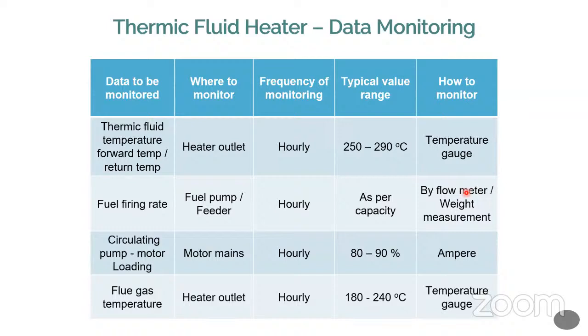It can be measured with the help of power, not the ampere. Ampere measurement is not correct. It should be a power measurement because sometimes the power factor also depends on the load condition. When the load is very high, the power factor is also very high. Therefore it is recommended to measure the power, not hourly, but at least once a day you have to measure the circulating pump power.